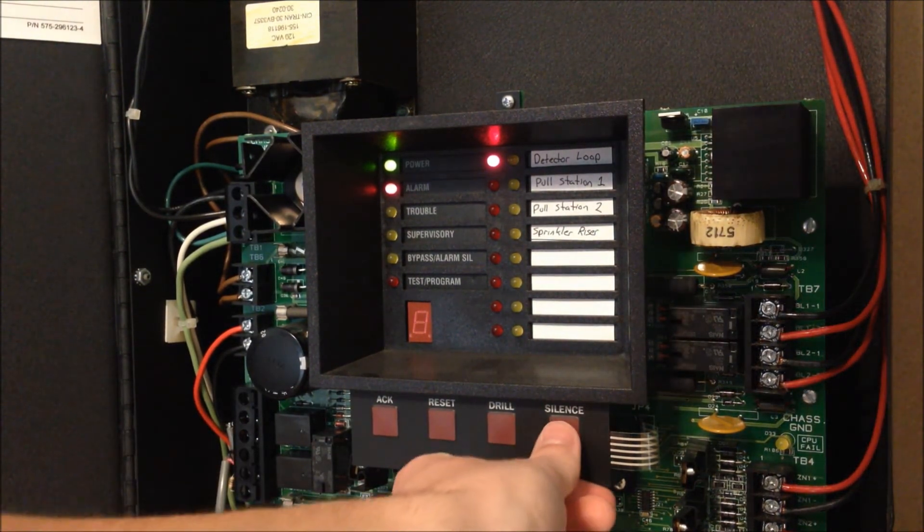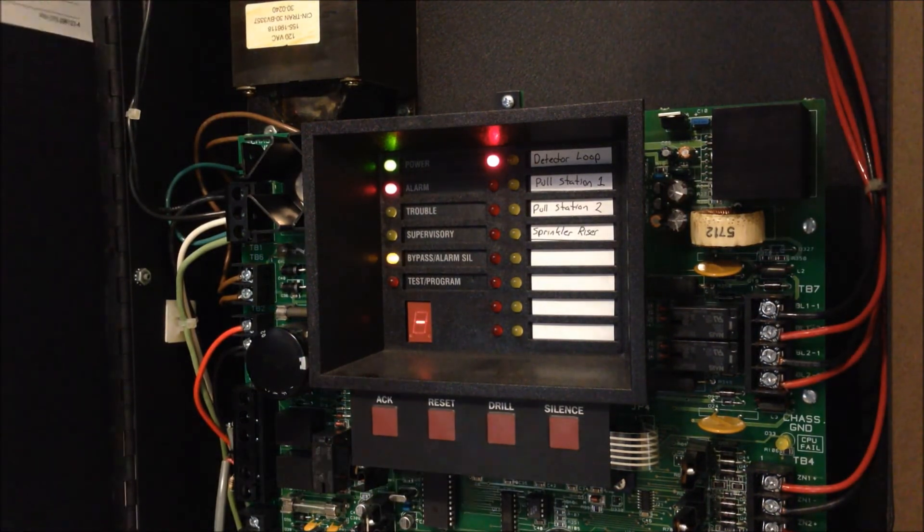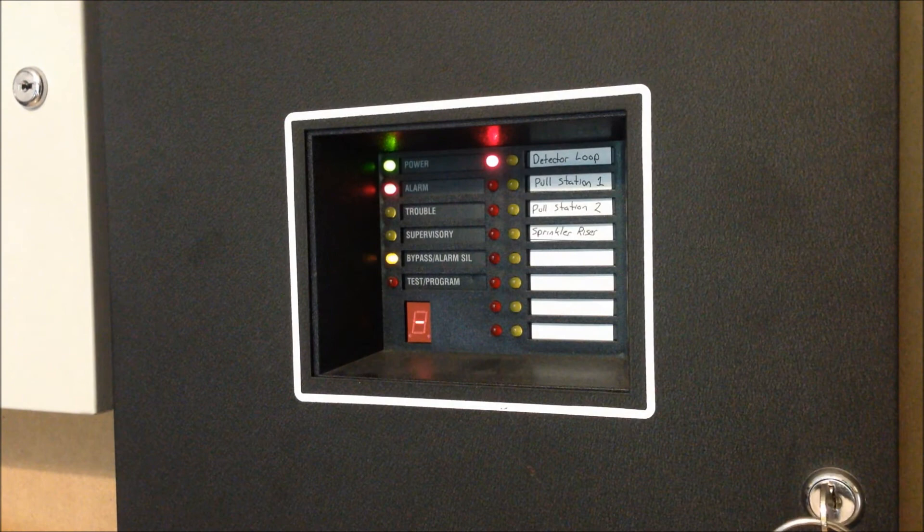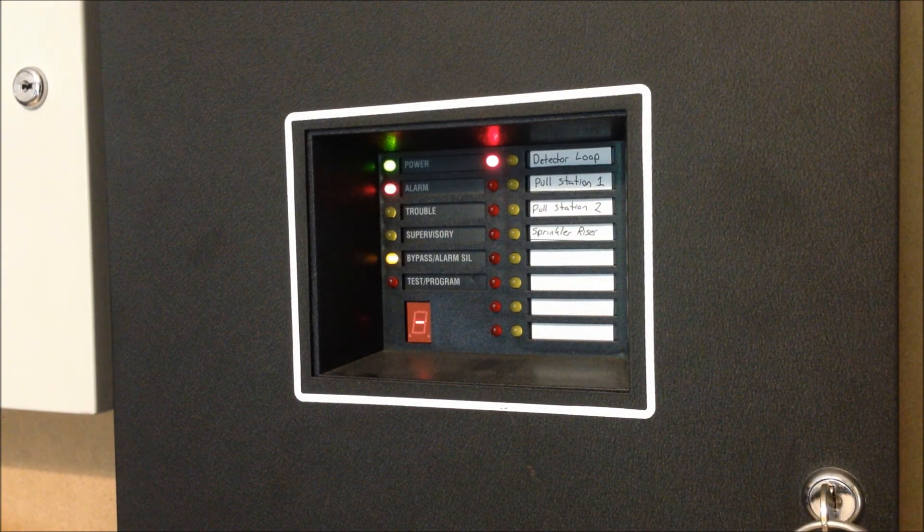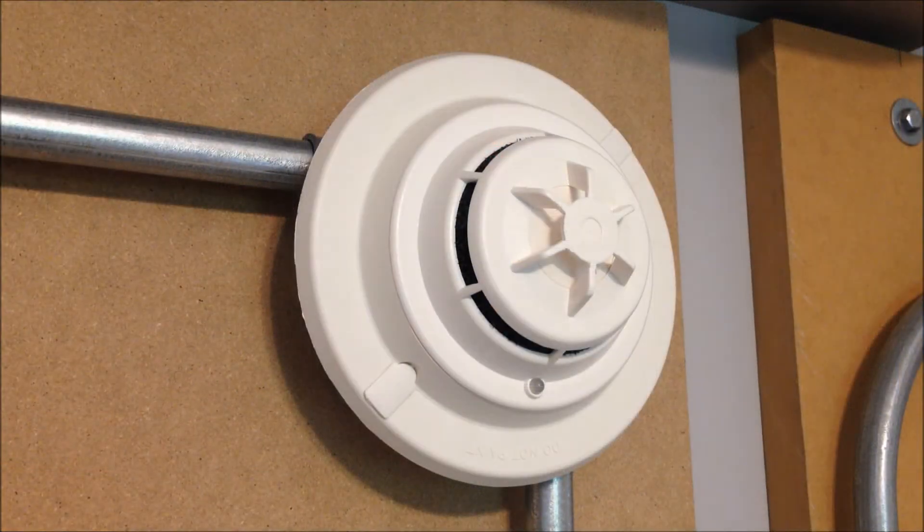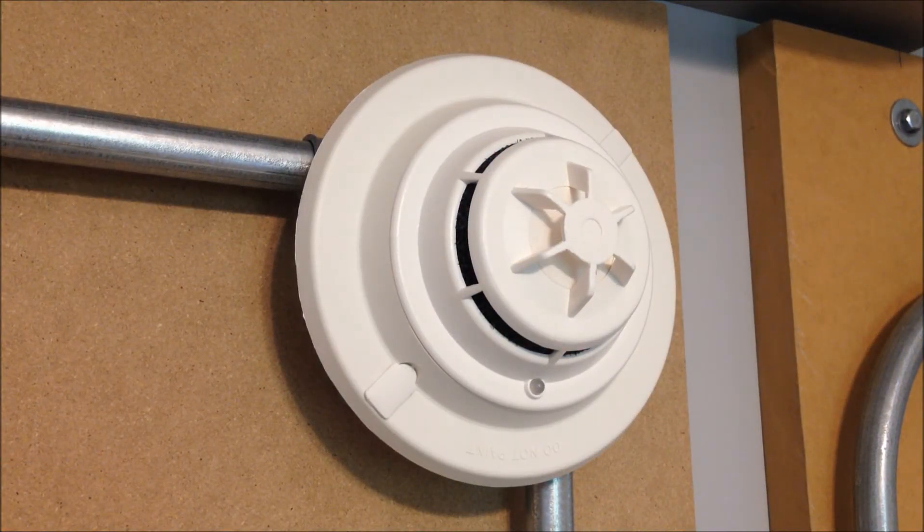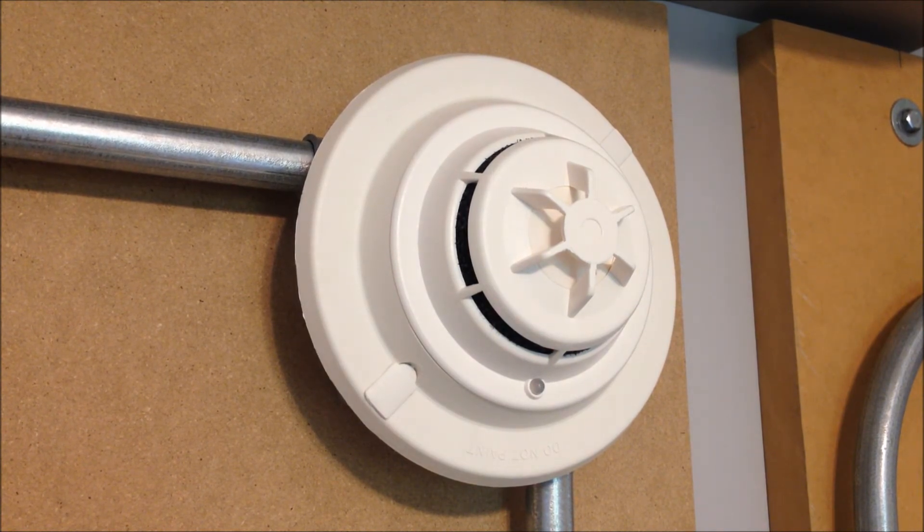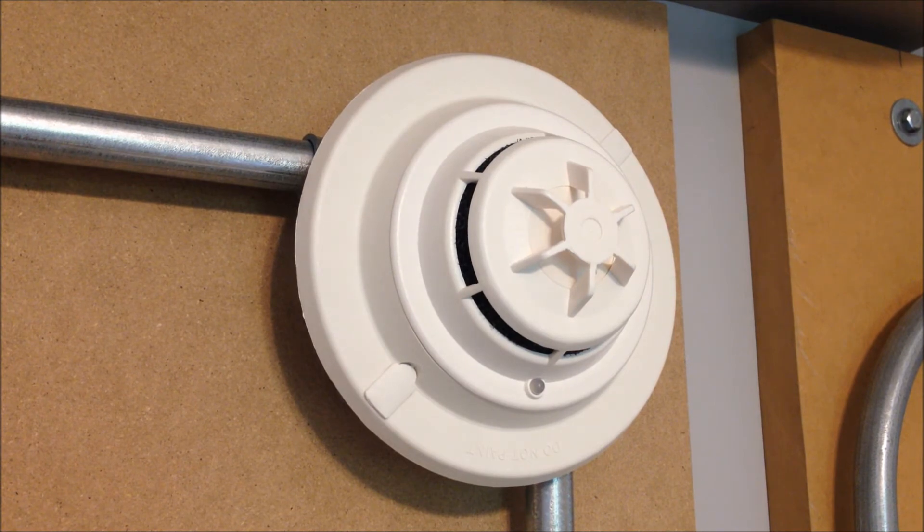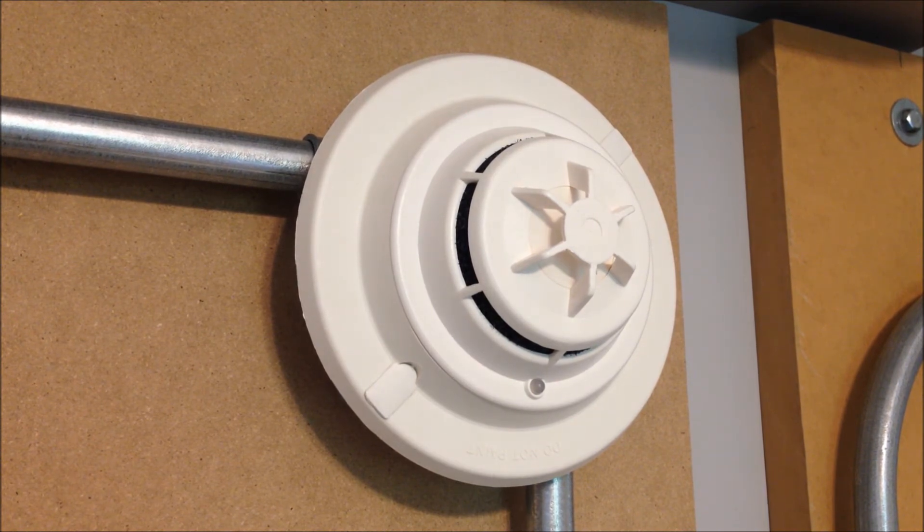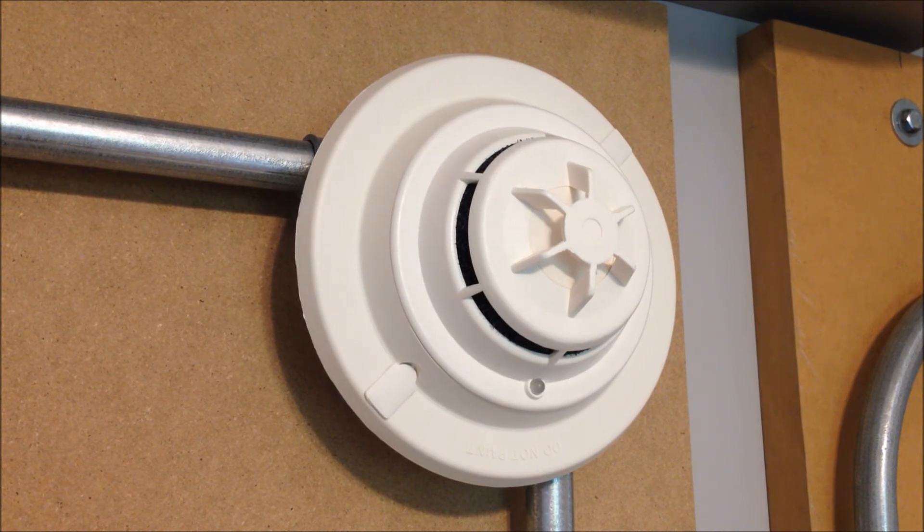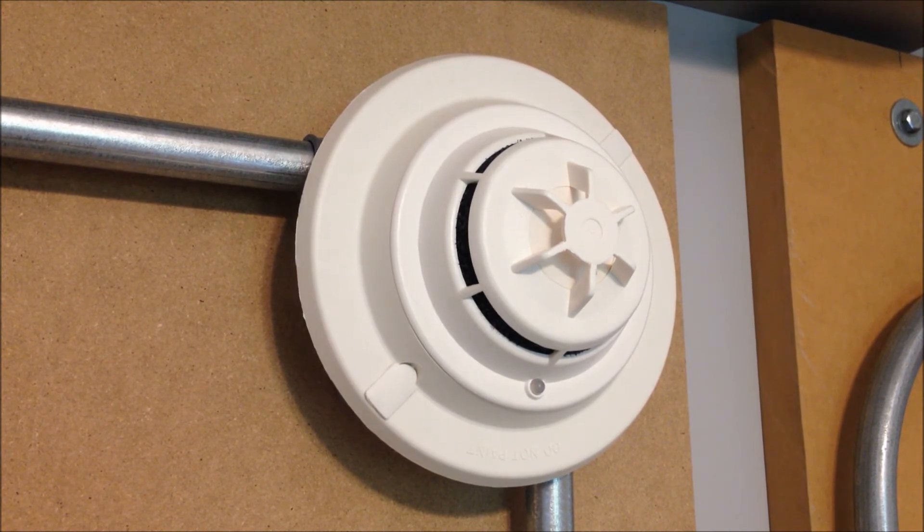So we're going to go ahead and silence that. I'll reach over and silence these keypads. So as you saw, it took a while to activate, but now we finally do have the red LED on the detector flashing, showing that it's in the alarm condition. I'll have to look back at the video later. I didn't think that there was alarm verification on this zone, but it certainly seemed like it because I think the red LED started flashing far before the system went into alarm. So we're going to go ahead and move down to one of the pull stations and activate the system again like I normally do.